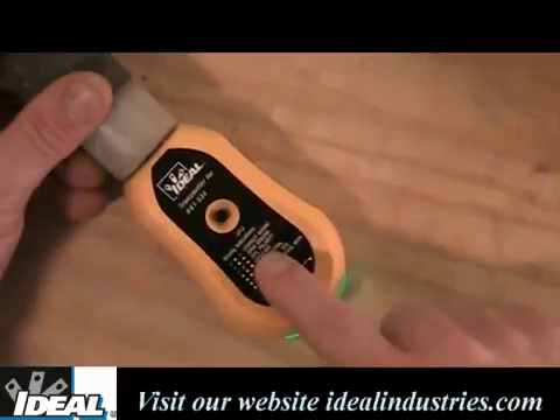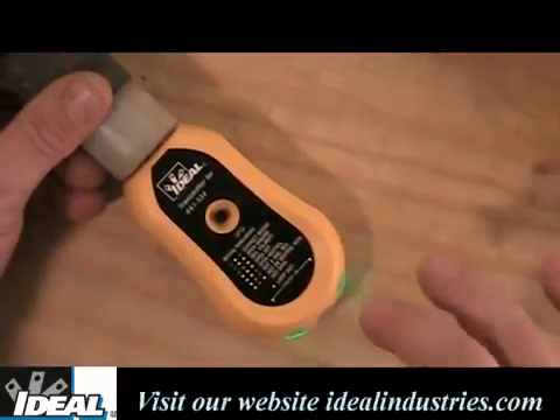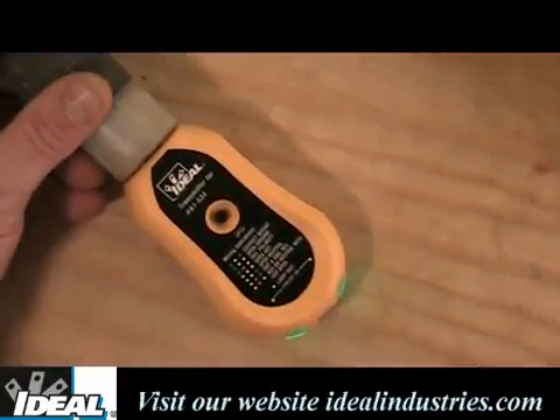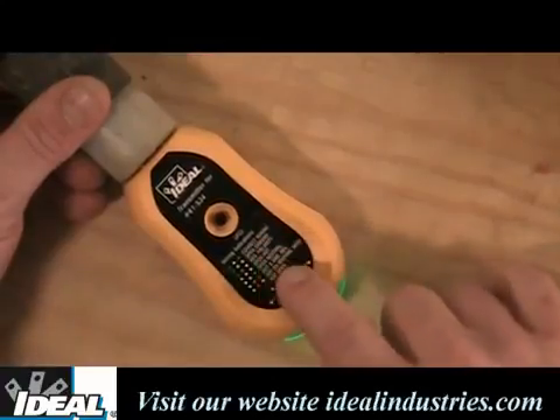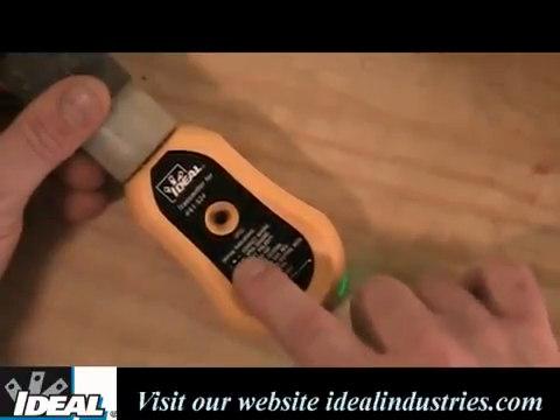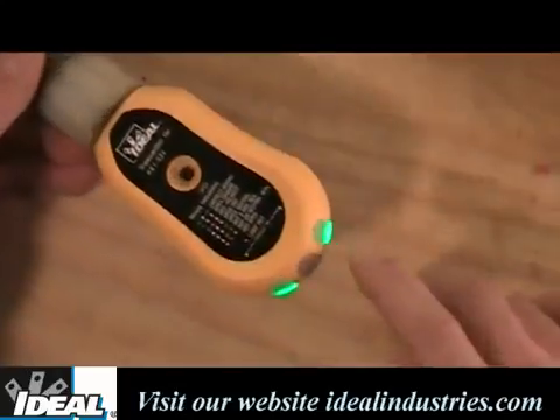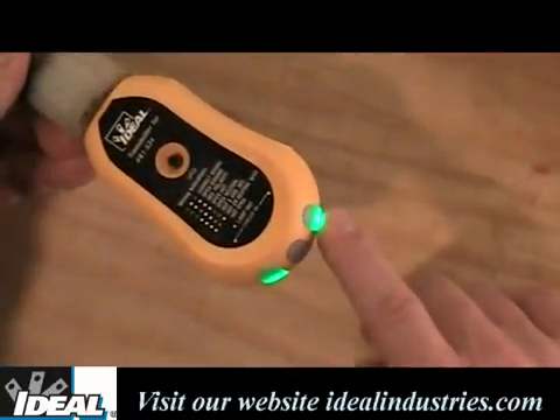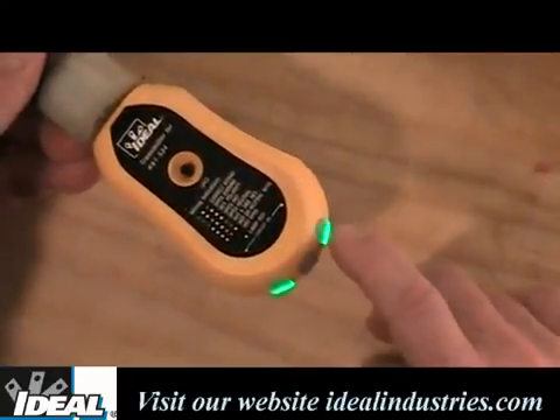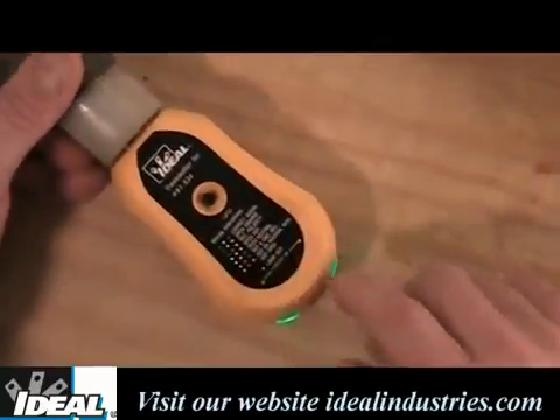Now, the tester can also be used to identify whether or not you have correct wiring at the outlet in the room. This little legend here, with this combination of lights being lit up, will indicate what's going on with the electrical wiring at the outlet. Now I have two green lights here lit up, and the middle light is not lit up.